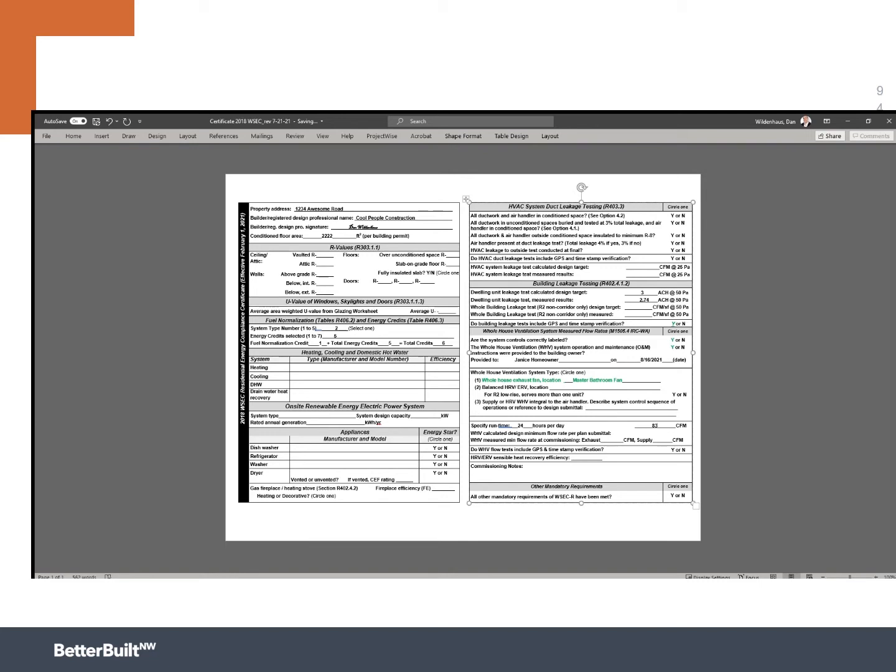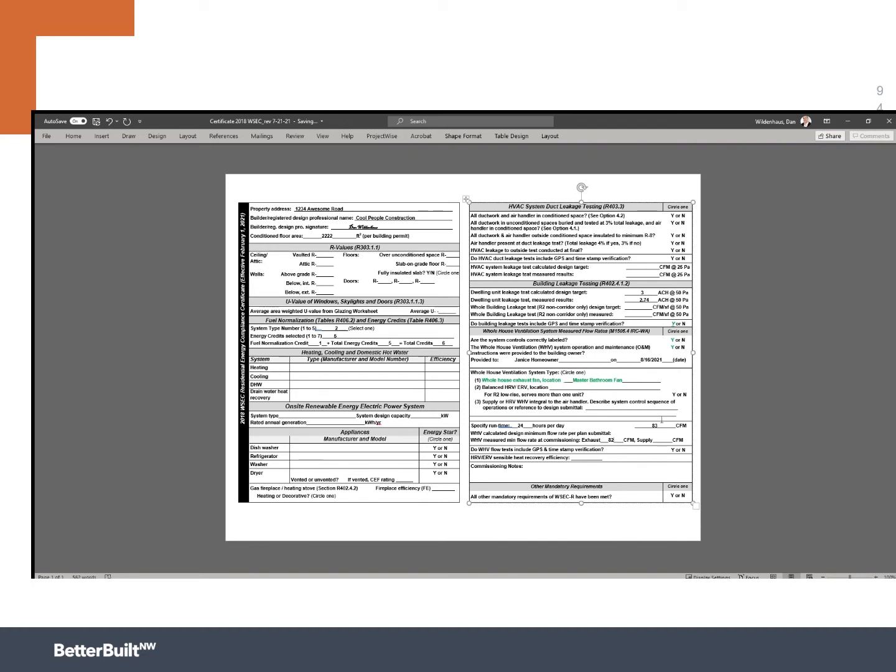Well, depending on how we set it up, it was 83 CFM if we were doing it just for exhaust only. And then how was this actually commissioned? What did we actually get when we commissioned this? So when someone actually showed up and used a flow pan, a flow hood, a bellometer, any of those tools that are common for doing this, we could measure it. And let's say we perform the measurement and it was 82 CFM. That's pretty darn close. Usually within 1% is the tolerance allowable there. That is, by the way, a recommended practice. Each jurisdiction may get on you if it's not meeting exactly so. Maybe you want to put in, again, we talked about putting in a 90 CFM fan. So if we did that, it would likely to be tested at something like 89.